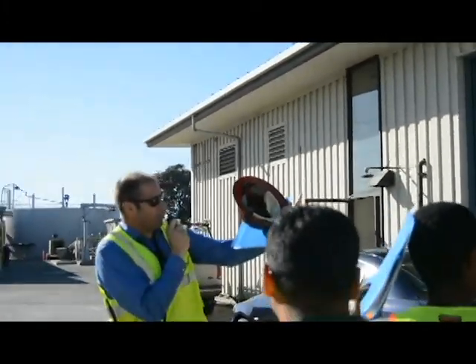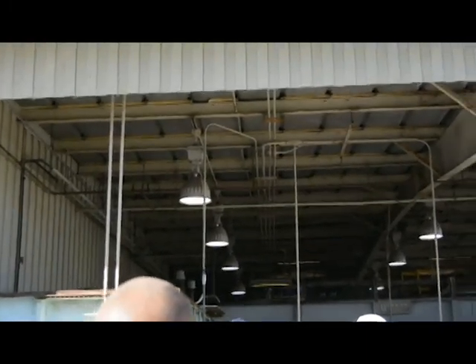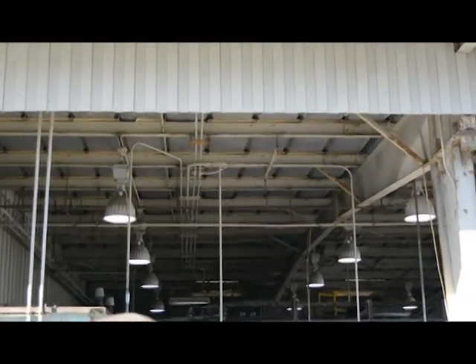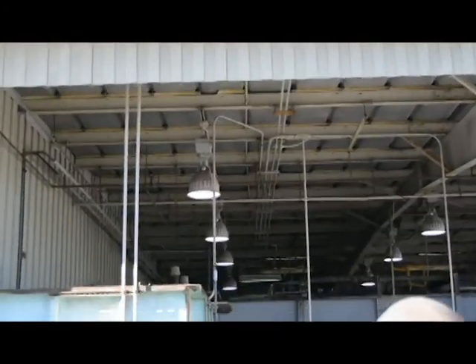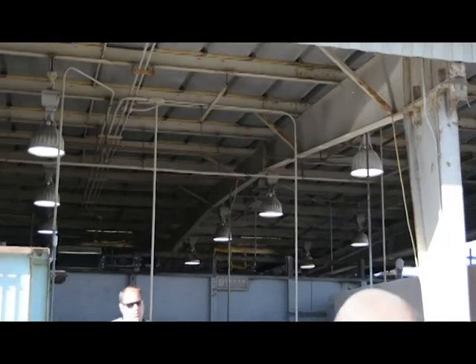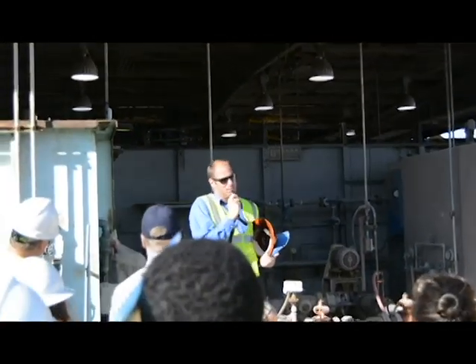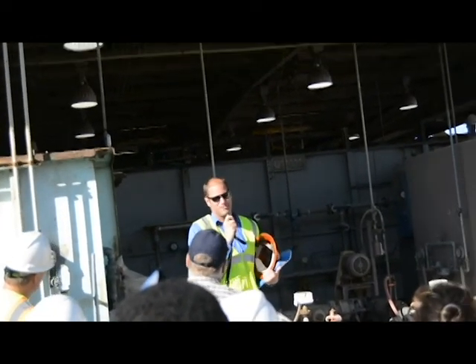If you see the upper rails on the dissolved air flotation tanks, those Baker tanks over there, the front of them, that metal rail has basically disappeared. You can walk in there and take a look at it. There is no metal left. There's nothing to weld to anymore. And so the minute it falls apart, the chain walks off the cog. We have to make this last for 2 more wet weather seasons, which gives our maintenance group a fit.